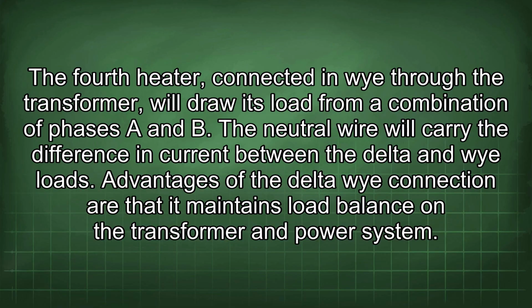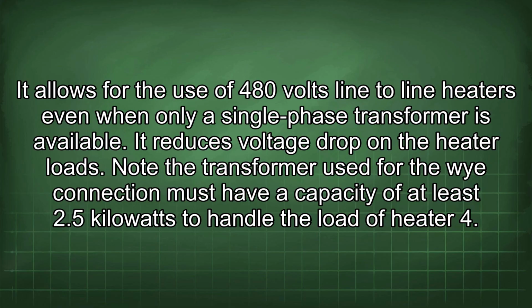Advantages of the Delta-Wye connection are that it maintains load balance on the transformer and power system. It allows for the use of 480 volts line-to-line heaters even when only a single-phase transformer is available. It reduces voltage drop on the heater loads.